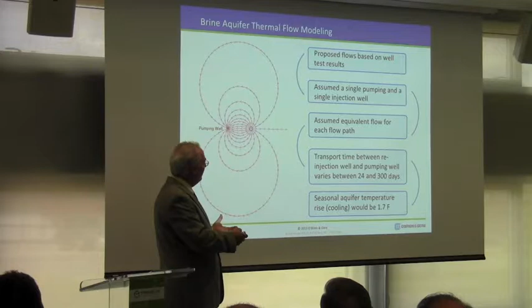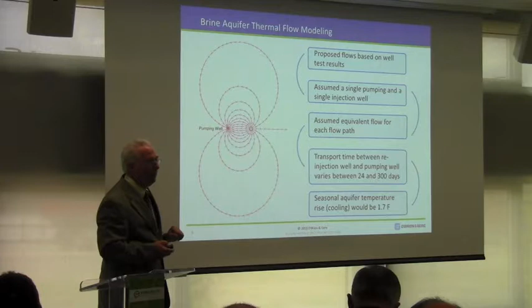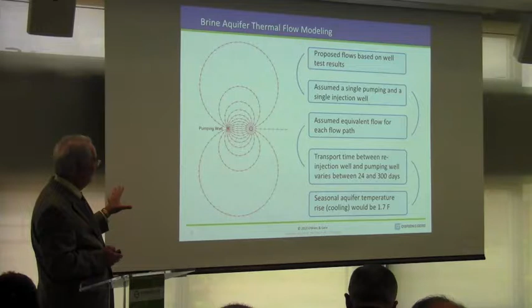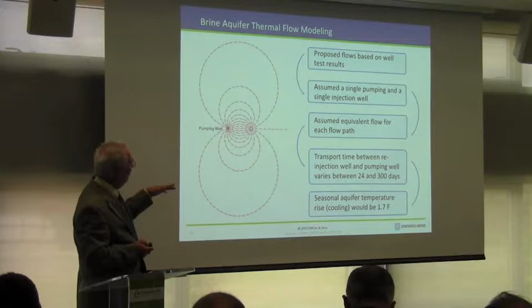With this model, we also looked at the number of equivalent full load hours during the cooling season and heating season, mostly the cooling season, to see how much this system would heat up the aquifer in this area. It turned out to be conservatively about 1.7 degrees Fahrenheit for this whole area with full seasonal operation. So not a lot, and we neglected any heat transfer around the perimeter or losses to the environment, and we assumed no transport at all in the brine aquifer, that this was steady state. I think it's pretty stable, but even small amounts of migration, a foot or two a year, would have a big positive impact on system performance.